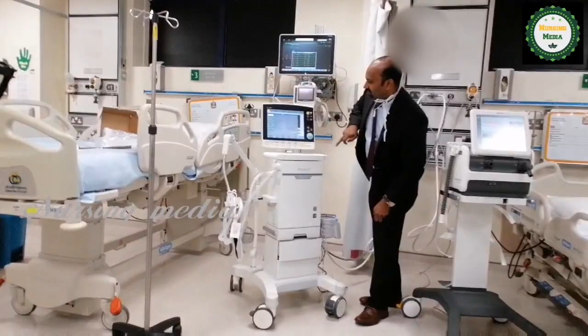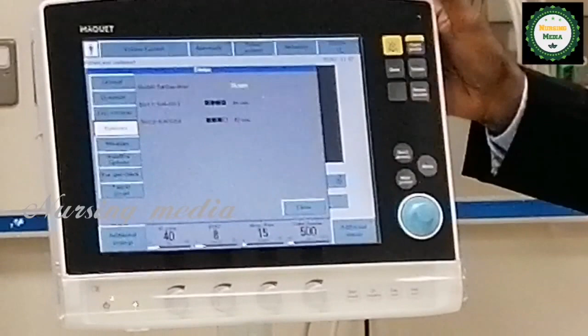You see here, when you tap your status, the status will tell batteries. When you tap batteries, it's saying that I have 2 batteries, and charging is on, it's not charged. Fully charge it. It's saying each battery is 44 minutes, 42 minutes. It's an ICU ventilator, you don't use it for transport purposes, but you have minimum 1.5 hours backup. Please charge it. All the ventilators, put them on charge, engineer, please. 1.5 hours each minimum, but put it on charge and it will tell you how many hours, no need to calculate. You could see here now, 44 and 44 for example. So once it is fully charged, we can put it off?